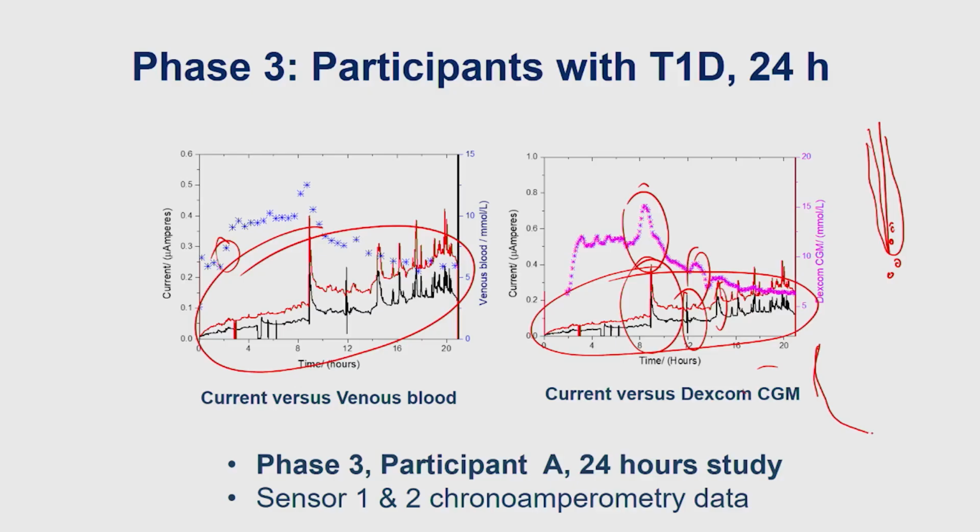Plus the other thing is also with electrochemical sensors, when you start, you always have this drift. It goes from a high current value towards a low background value. In the plot here, it seems to go a little bit up. Is that because of drift? That's sensor drift. These are examples of drift. This is where you have a sensor warm-up time. These are also going up, and then they start to monitor peaks here.